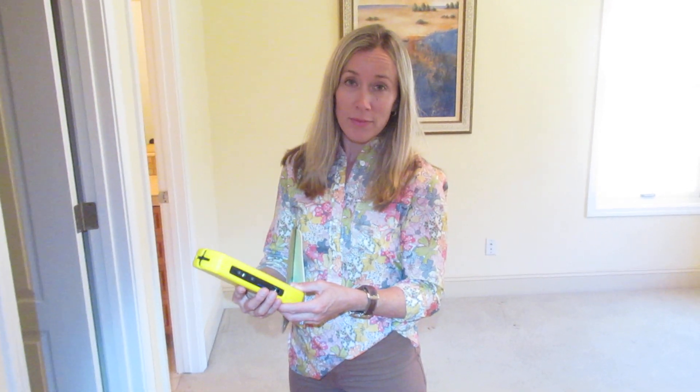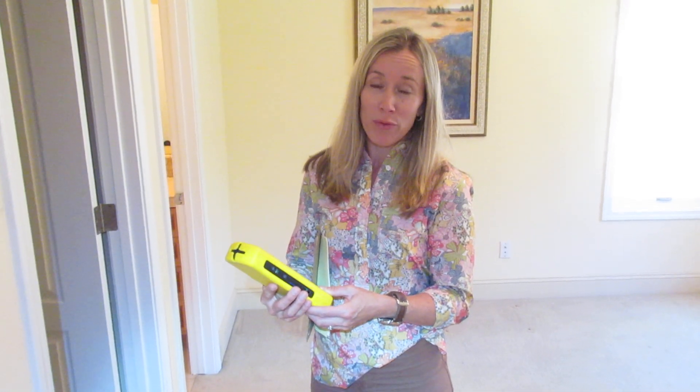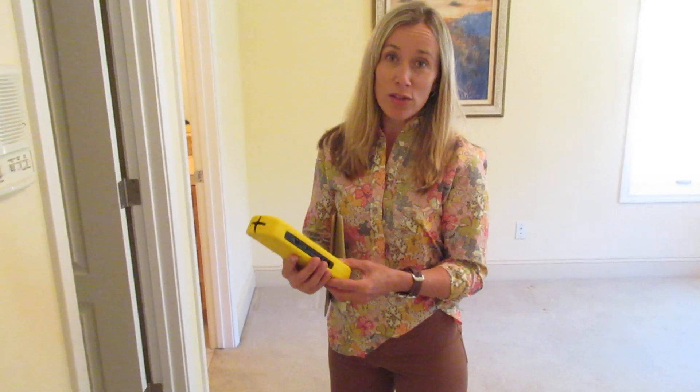Can this be fixed, or should these people look for another house? This can be fixed, luckily for the new homeowners. It's going to involve taking lots of AC magnetic field measurements with our 3-axis gauss meter, determining the areas in the home with elevated fields, marking those switches correlated with the high AC magnetic fields, and then coming back with an EMF-trained electrician to resolve any neutral-to-neutral or neutral-to-ground issues. You cannot just send any electrician — it's a collaboration between the building biologist and the EMF-experienced electrician to solve these wiring errors.